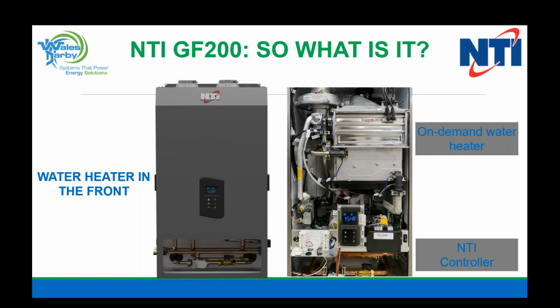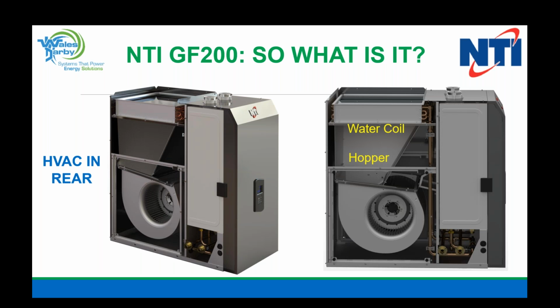So truly, what is it? Well, it's a water heater in the front, and it's a Navien water heater. It's an on-demand water heater, tankless water heater, however you guys refer to them. So NTI has taken that product. They've added in an NTI controller and an NTI three-way valve and an NTI flow switch. And we have added to the back side of it, so it's hot water in the front and it's HVAC in the rear. So we've added a blower, a hopper, and a hydronic coil. So you would look at that as a typical air handler type deal, hydrocoil unit. So we have the ability here with the tankless water heater to produce hot water for the home and to produce heating for the house.